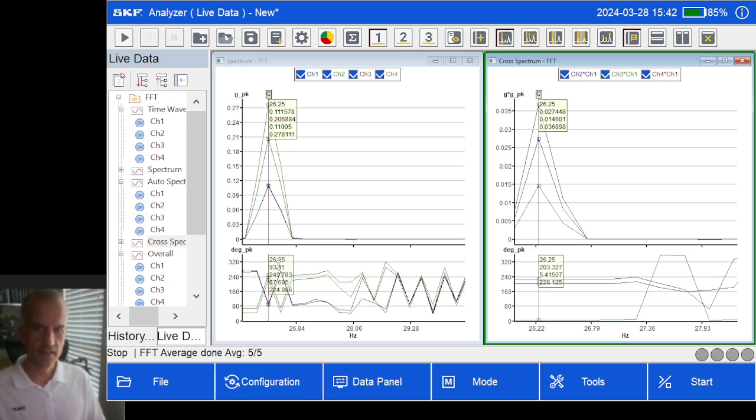If we look at the phase, it's cross-channel phase. Again, I'm not using the speed. It's just comparing these signals. It's looking at the real and imaginary portion of the complex FFT and the cross FFT, doing the root sum square of those two values at each individual bin to give you the amplitude in the FFT, which is what we usually are interested in.